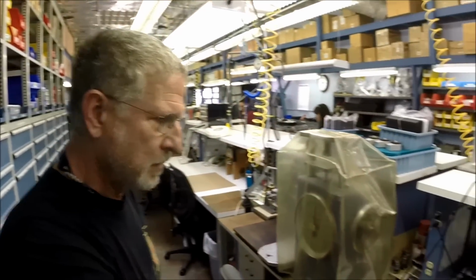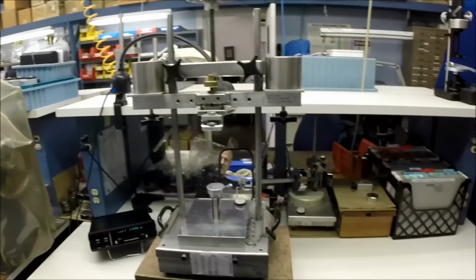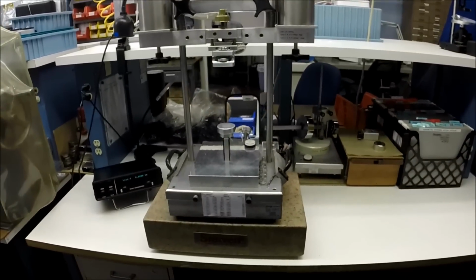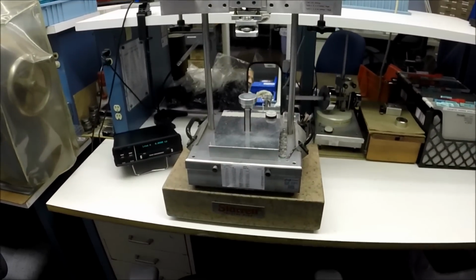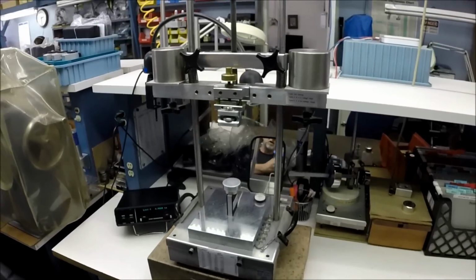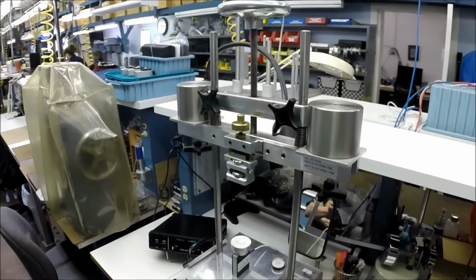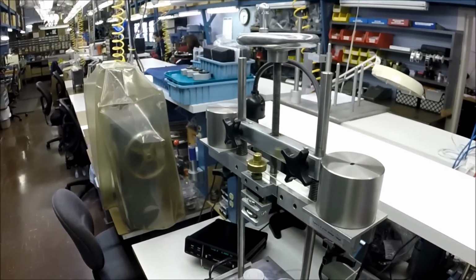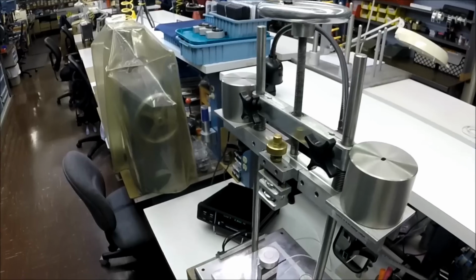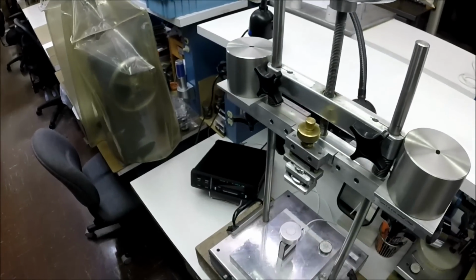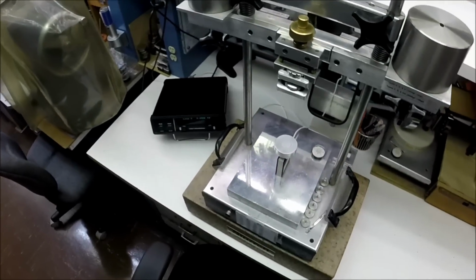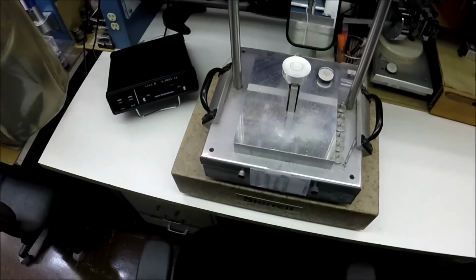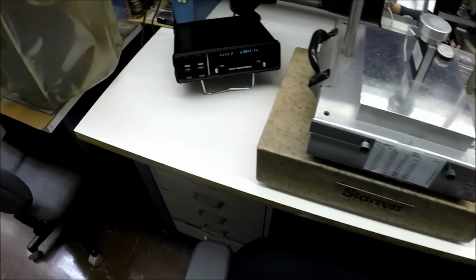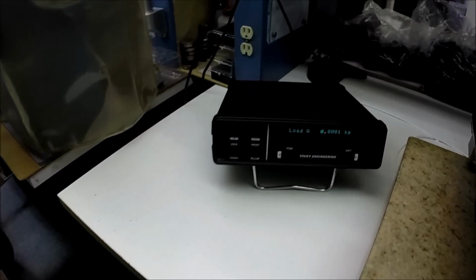Behind you, to my right, this is an electronic load cell, very precise, that can do the same test we saw on the durometer calibrator, but this is totally electronic and done by hand, and you compare the dial reading of the durometer to the actual load in grams on the readout. So it's the next step up in precision.